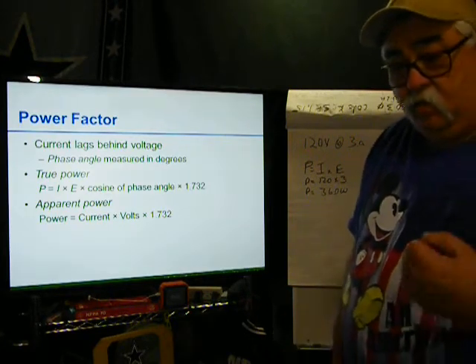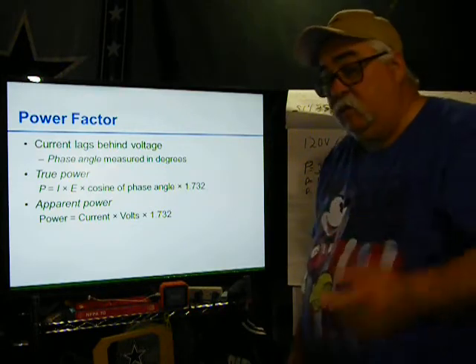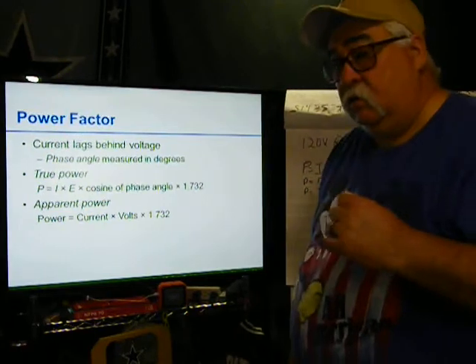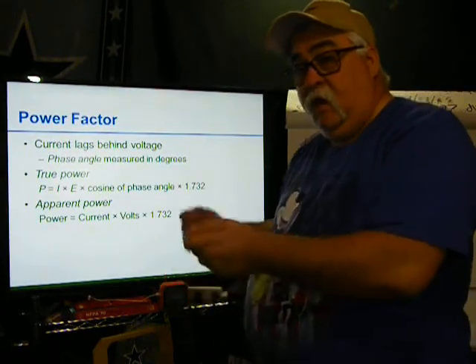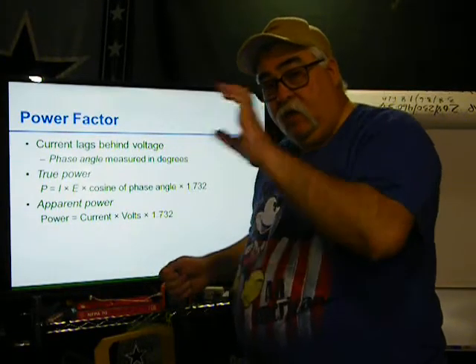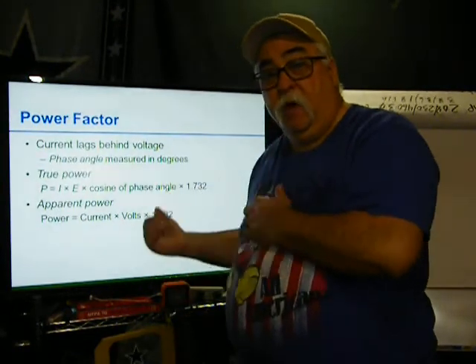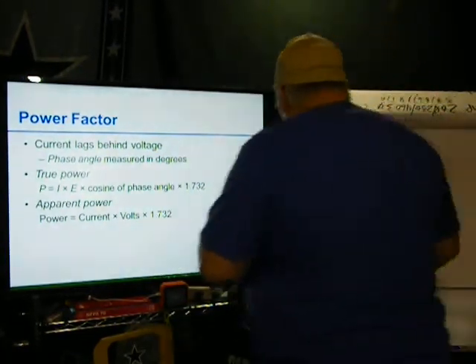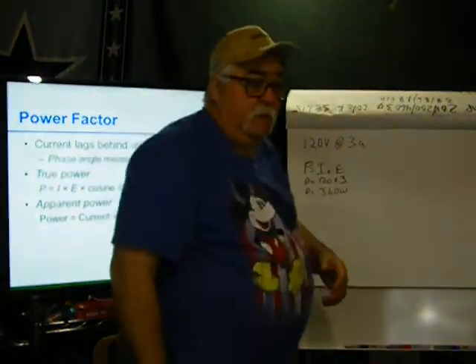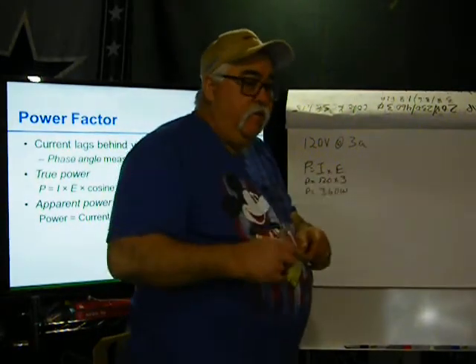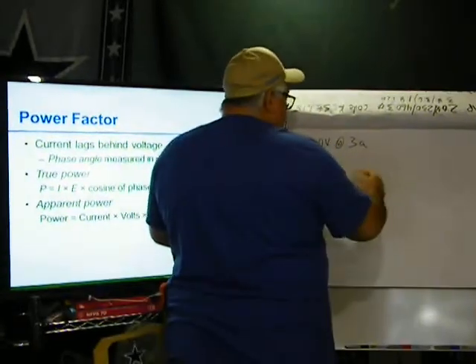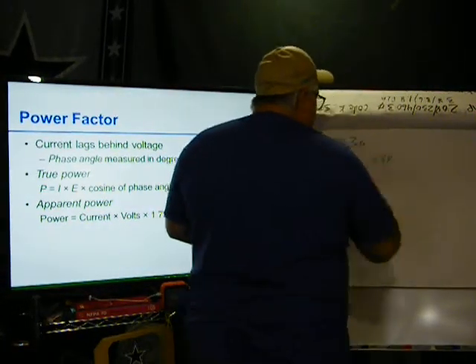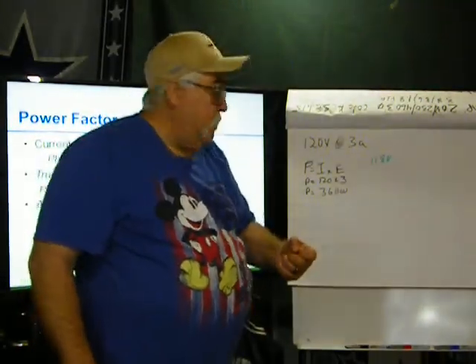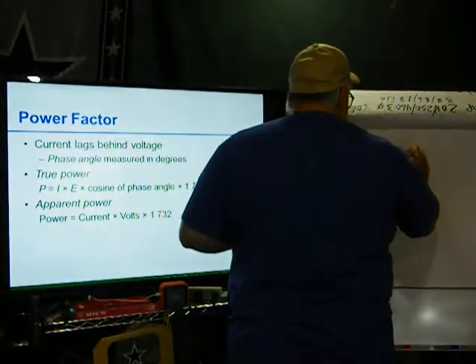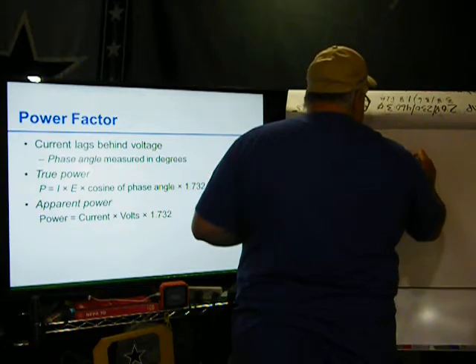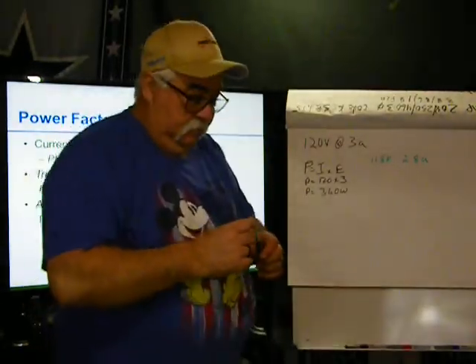And the reason they want to clear this out a lot of times is to make sure we can get in. Our residential book covered it a little bit better. The residential book talked about taking a reading with your watt meter, and then taking an amp reading. So you get the actual wattage and the actual amperage, and multiply it by the applied voltage. This is simple math looking at a nameplate. I go in there and read, and instead of having 120 volts, I have 118 volts. Okay? And I get my clamp on, and instead of having 3 amps, I have 2.8. This is an example.